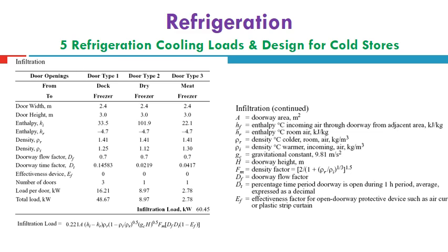It should be clear that door type number 1 gives 48.6, the larger amount, and door type 2 and door type 3 give a smaller amount because the temperature difference is less between the freezer and the meat freezer compared to between the dock and the freezer. Finally, the total infiltration load is listed here as 60.45 kilowatt.